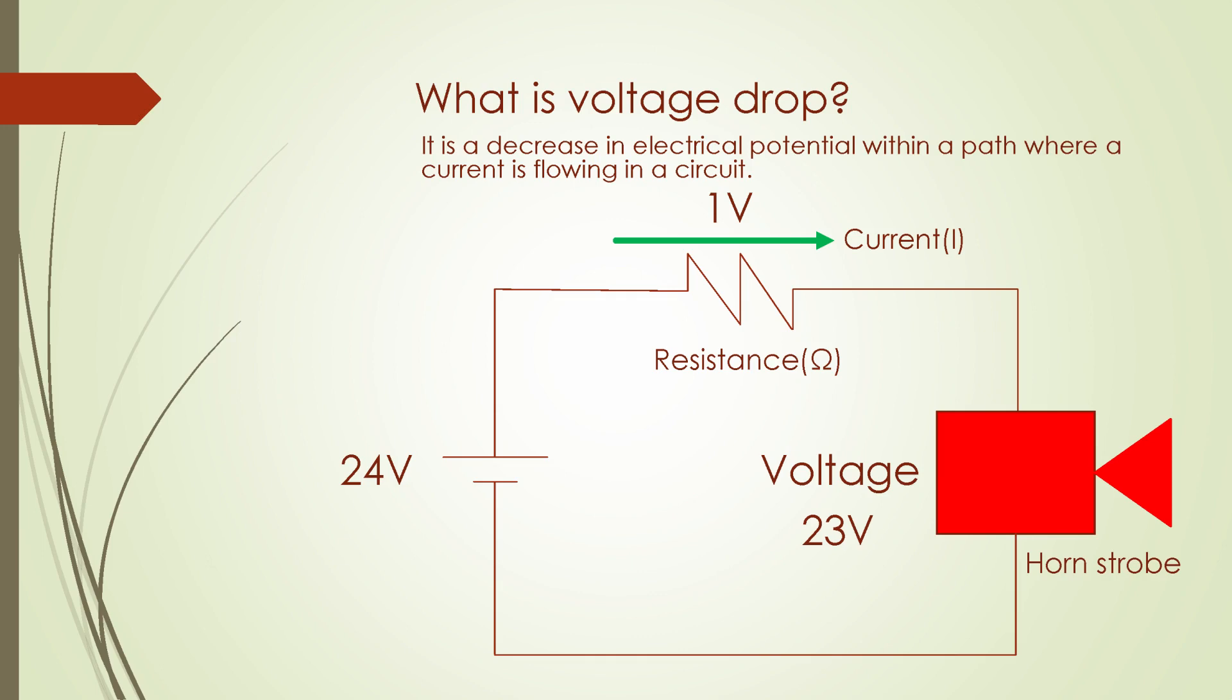What is voltage drop? It's important to know the basics and fundamentals of electricity so you can start working with the calculation of voltage drop. Voltage drop is the reduction in the amount of electrical potential within the electrical path where current is flowing. As you will see in the example illustration, the 24 volts power source is supposed to deliver this amount of voltage to the fire alarm horn strobe, but because of the voltage drop of one volt within the conductor, the horn strobe receives only 23 volts.